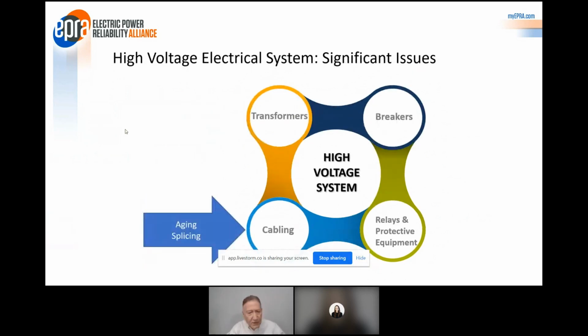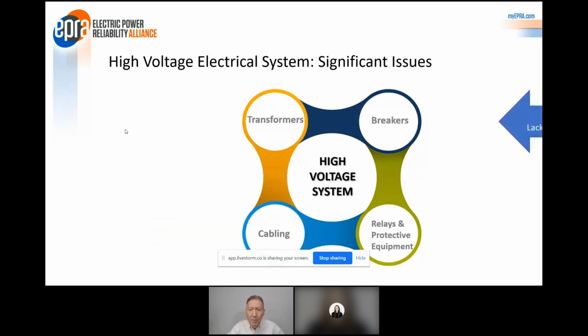Cabling - you've got splices everywhere. Cabling is right along with transformers in terms of aging, and they don't last forever. We see more water trees now than we've ever seen, and they tend to happen with deterioration. It's not like you have rotating equipment here - you've just got a buried cable, but it deteriorates over time. The insulation sheathing deteriorates, and splicing is a major issue where you get problems.